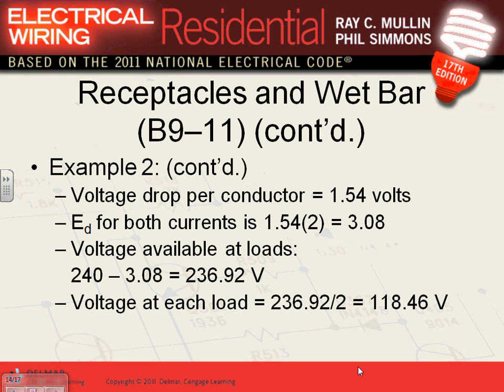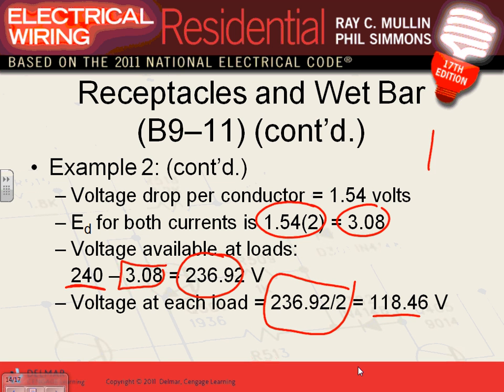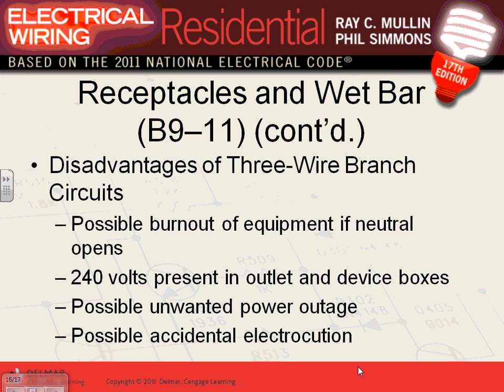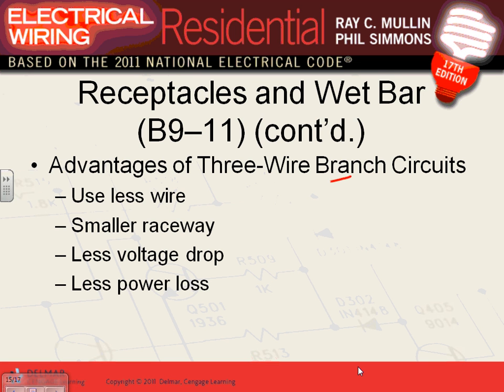Look at the voltage drop. The voltage drop in each circuit is the same thing. You got 3.08, but the 3.08 is coming out of the 240, not the 120. That's a major difference. The voltage drop is still the same, but it came out of 240 because they're as if they were connected to 240. We cut it by half because it's going to be shared. That will get you 118. Before it was 116 volts. So if you use a multi-wire branch circuit, you gain 2 volts in the voltage drop. Is that good, bad, or ugly? Good. Another advantage of multi-wire branch circuits: less copper, less voltage drop, less losses in the line. Okay, so that's basically what I have for you. Again, multi-wire branch circuit: less wire, smaller raceways, less voltage drop, less power loss in the line.